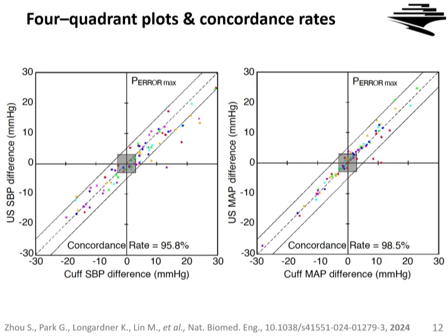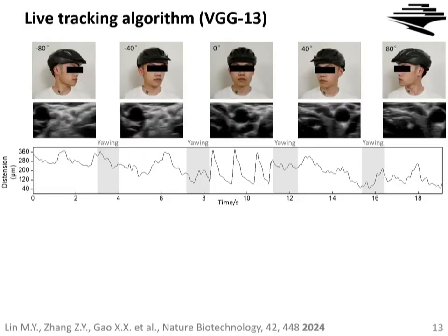And we analyzed those different daily activities in these 4 quadrant plots. You can see this is ultrasound data, this is the cuff measurements. Ideally, all those data points should fall on this dashed diagonal. In reality, you can see those data points fall within plus or minus 5 millimeters of mercury. That means the measurements between those 2 modalities are within these FDA-defined regulations. And this is the systolic blood pressure and mean arterial pressure. We can do the same thing for diastolic blood pressure.